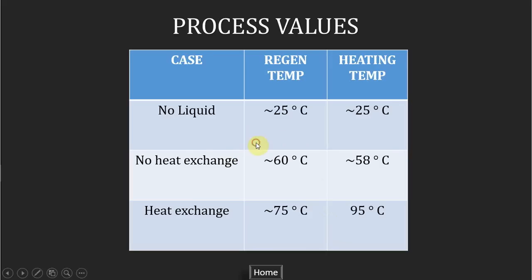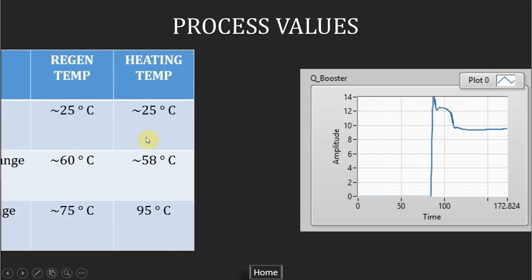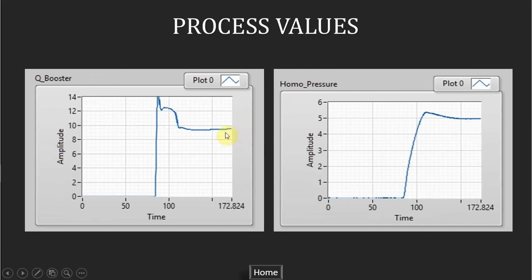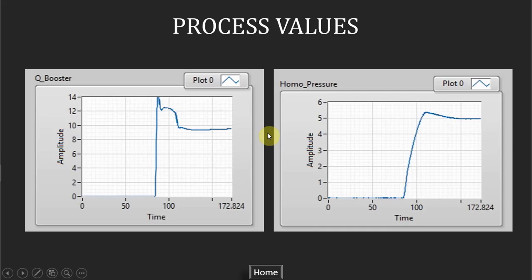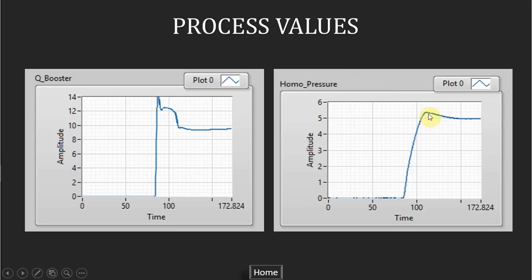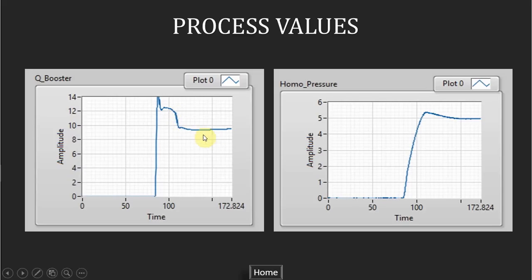How about the pressure? The pressure is controlled by a booster pump speed. The faster the pump is, the higher the pressure can get. The limitation of the pressure depends on the working pressure point of the homogenizer. As you can see in this figure, at this point the pressure is higher than the set point, let's say it's 5 bar. The speed of the pump will decrease hence the flow rate will decrease.